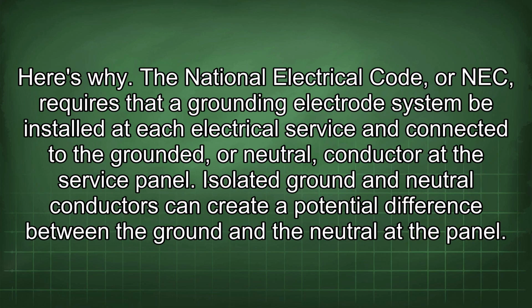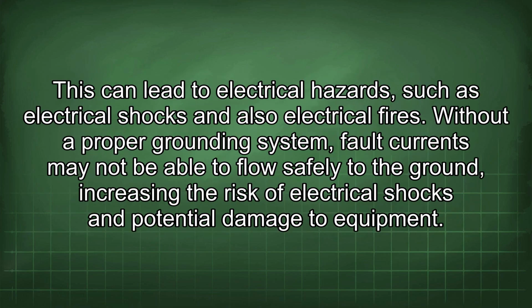Here is why. The National Electrical Code, or NEC, requires that a grounding electrode system be installed at each electrical service and connected to the grounded, or neutral, conductor at the service panel. Isolated ground and neutral conductors can create a potential difference between the ground and the neutral at the panel. This can lead to electrical hazards, such as electrical shocks and also electrical fires. Without a proper grounding system, fault currents may not be able to flow safely to the ground, increasing the risk of electrical shocks and potential damage to equipment.